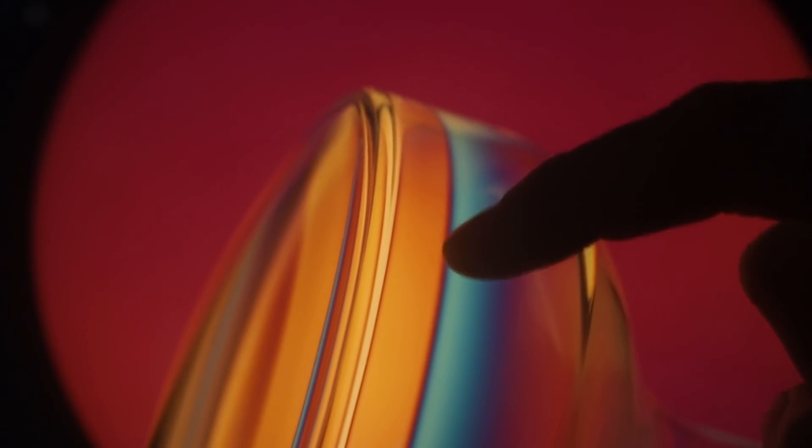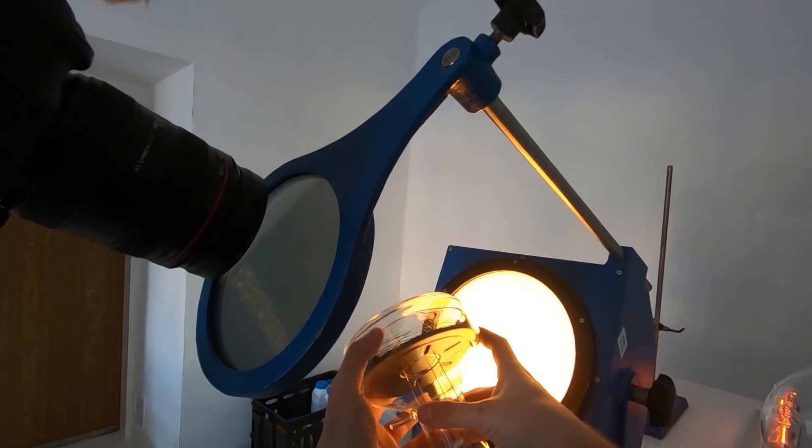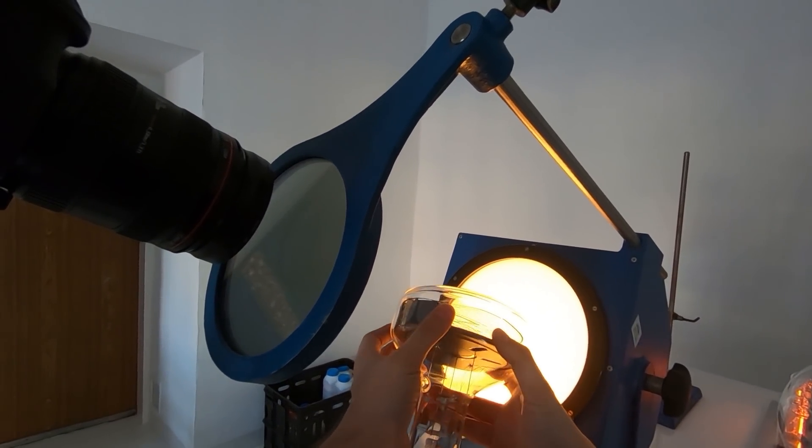You can see the sharp change in the colors here — this means that the stress here is quite significant. So we need to observe the tube to see if it is able to crack at this level of stress, because the tube can contain some stress but still hold up. You can see that the front window is quite clear, there is no stress, no border, but here the change between the colors is sharp, so there is stress in the side of the glass as well.